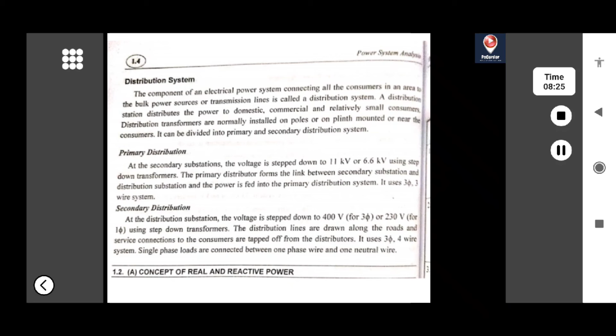In the secondary distribution, the voltage is stepped down to 400 volts or 230 volts. From the primary distribution, the bulk customers, those who are bulk industries, get their supply through 11 kV lines. In the secondary distribution, the voltage is further stepped down into 400 volt or 230 volt. 400 volt for a 3-phase 4-wire system, 230 volt for a single phase 2-wire system. It is called secondary distribution. This is the structure of the power system. The entire power system will be classified in this manner.